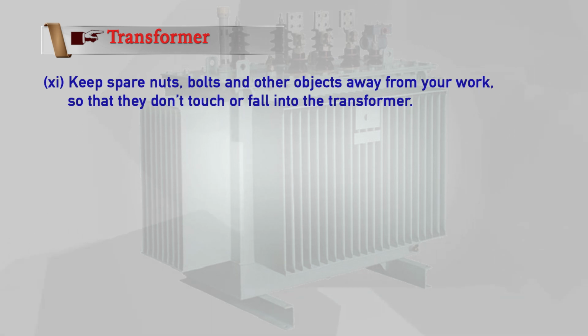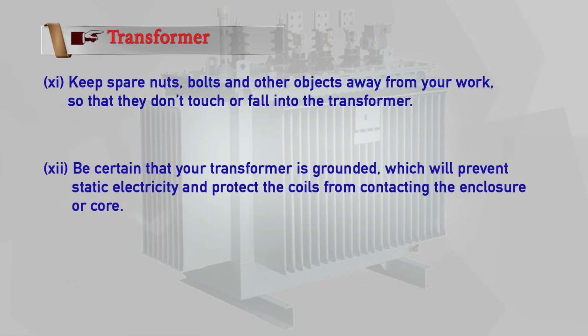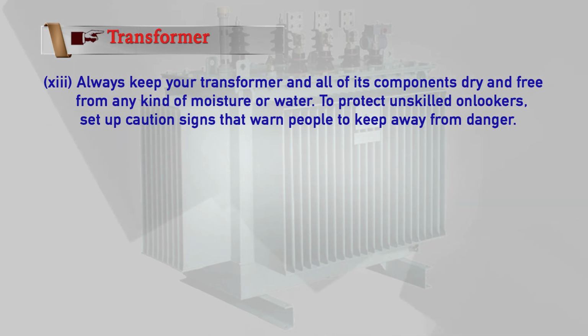Keep spare nuts, bolts and other objects away from your work so that they don't touch or fall into the transformer. Be certain that your transformer is grounded, which will prevent static electricity and protect the coils from contacting the enclosure or core. Always keep your transformer and all of its components dry and free from any kind of moisture or water. To protect unskilled onlookers, set up caution signs that warn people to keep away from danger.